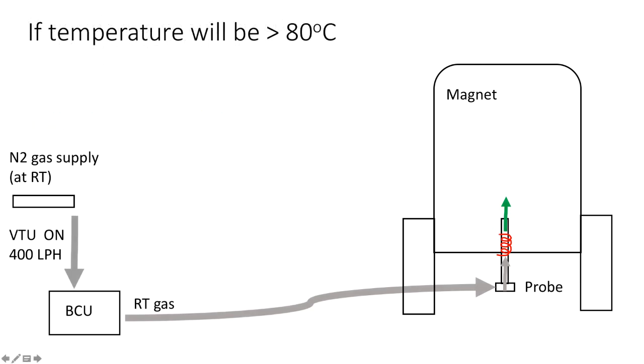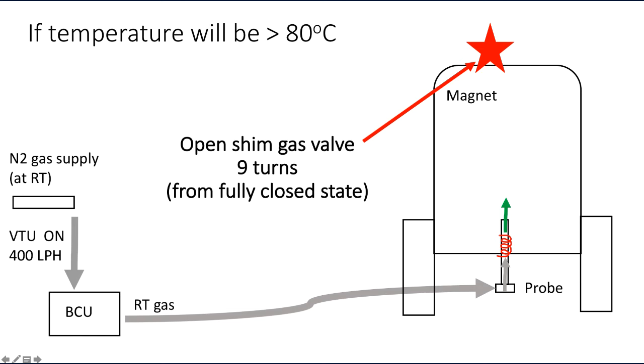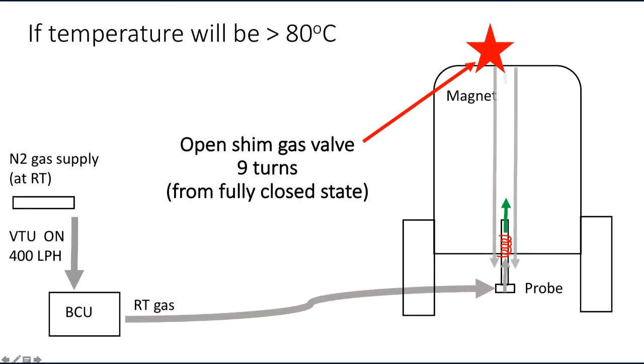If sample temperature is going to exceed 80 degrees C, we need to open shim gas valve 9 turns from fully closed state. This will supply a stream of nitrogen gas down the shim stack to cool the shim coils.